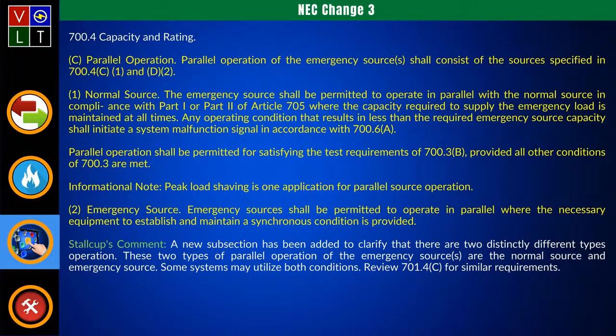And if that's the case, also go over and look at 701.4(C), where you get into legally required and optional standby. You're going to see some of the same similar requirements that are placed here also. So we correlated both of these to let you know. Is that 701 or 700? Well, this is in 700.4(C), but there are similar requirements over in 701.4(C). Gotcha. Okay.